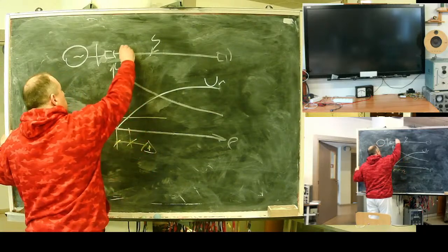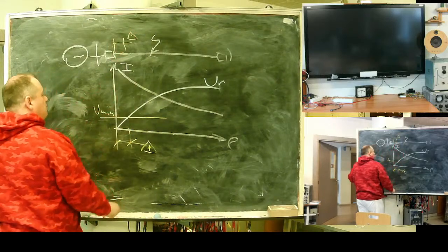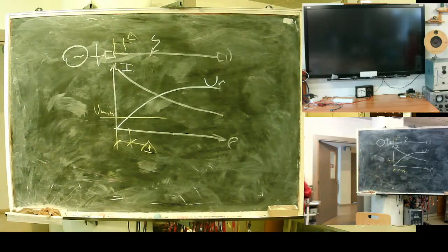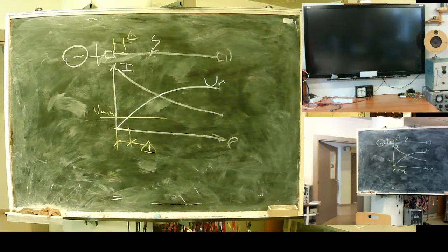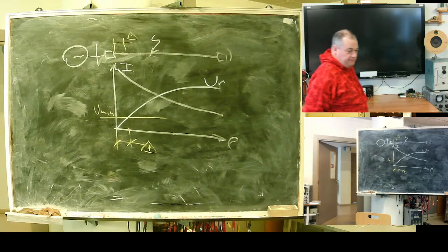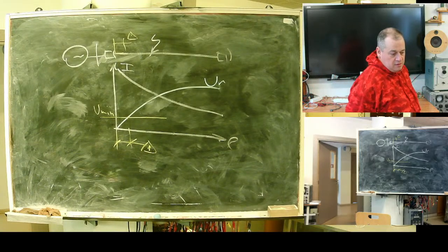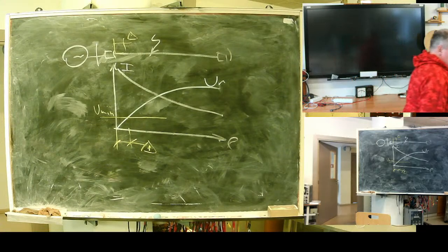You see, this part of line will be unprotected because it is not possible to calculate resistance. It's a problem. For many relays, characteristic has a blind spot at 0 kilometer. To prevent unprotected line, what's done?